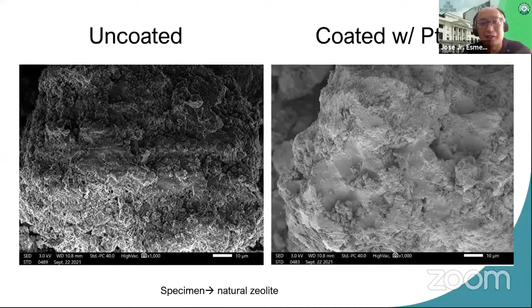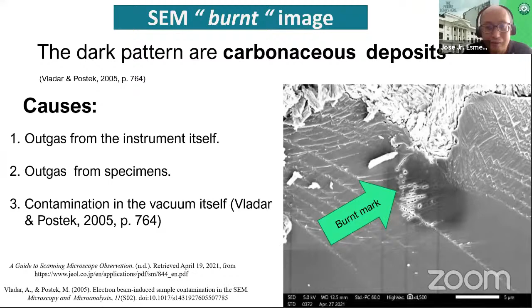Of course, one of the consequences is that some materials, especially if there are outgassing or contaminants, can cause carbonaceous deposits during scanning. These deposits create some sort of dark pattern or burnt mark. In SEM, they commonly call it SEM burn, but actually these are carbonaceous deposits accumulating on the surface. They are caused by outgassing from the specimen, or from the instrument itself. That's why it's very important that samples are well prepared, in order to prevent this kind of problem.